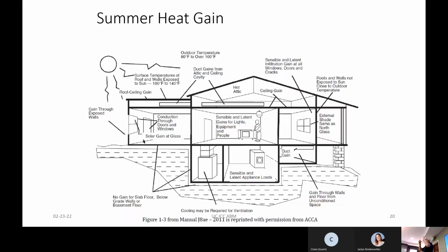But what do we do? We put a duct in an attic that has the greatest temperature difference we see anywhere in a whole house in summertime. Do you think they have 150-degree attics down here in summer? Absolutely. And you put a duct in it, then make it worse by suspending it above the insulation rather than burying it, and then you blow 50-degree air through the inside of that duct with an air conditioner. We have 100 degrees temperature difference between the inside of the duct and the hot attic, and we're only stopping the heat with R8.